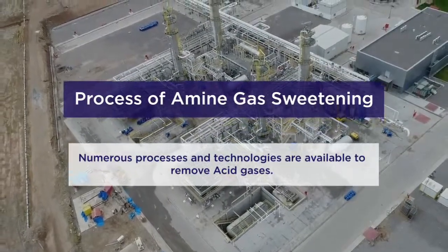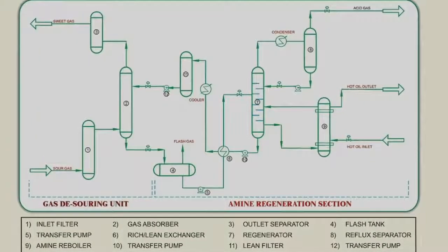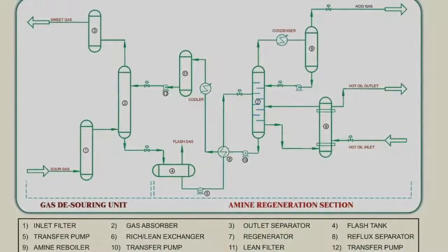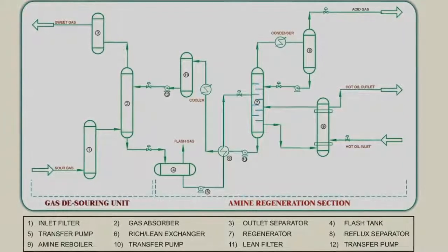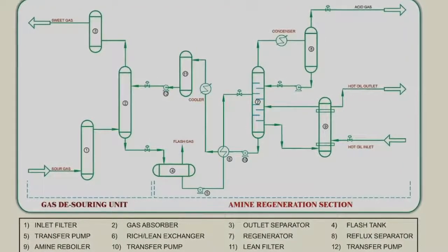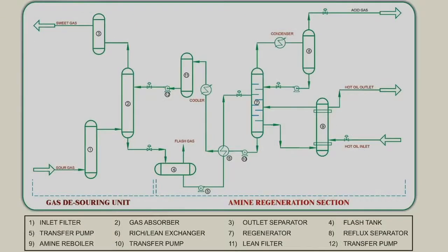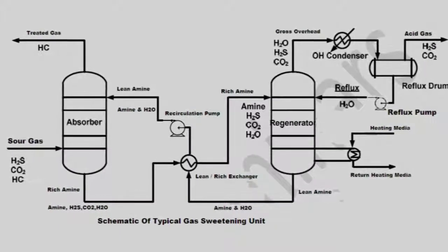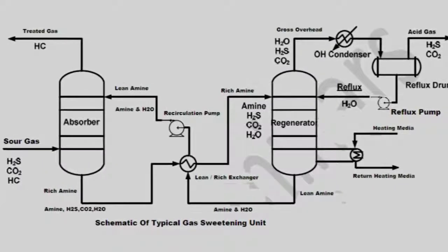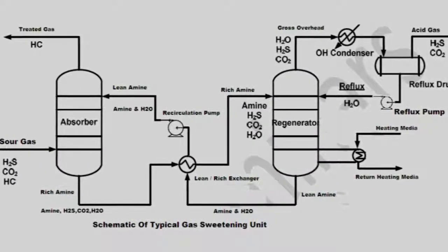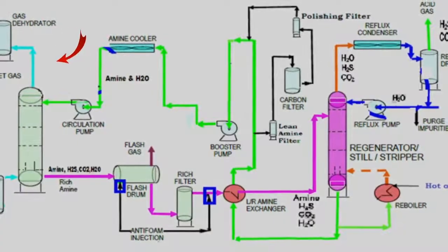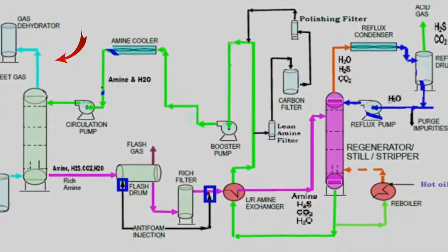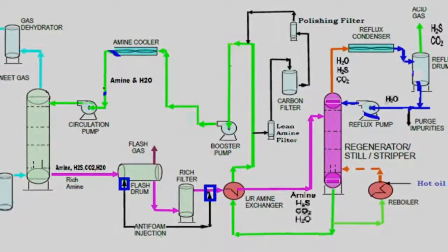The most common technique to remove hydrogen sulfide, carbon dioxide, and water vapor is to first direct the flow through a tower containing an amine solution. After contaminant removal, the gas flow is directed to filters for removal of mist, and then purified sweet gas is sent as the saleable gas. Following acid gas removal with an amine treatment unit, natural gas is generally processed through gas dehydration units.